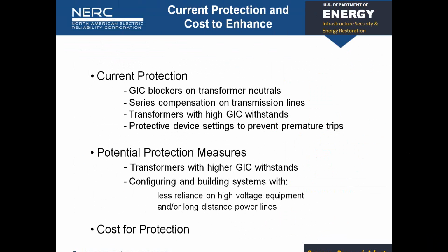Problem is the cost is much higher than the blocker. It might be 5 to 25 times. A lot of data out there, so who knows exactly, but more than actually just protecting with a blocker. So it doesn't make a whole lot of sense to say I want to put series compensation in as a space weather protection measure. But it gives you that protection if there's other reasons to put it in.